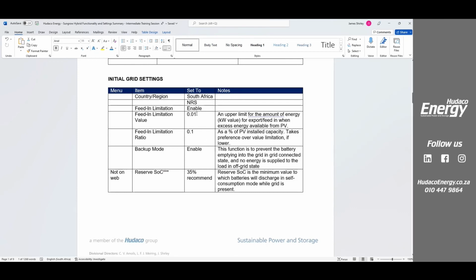Now, in fact, on the new firmware version, we just put 0 and 0, but there might still be some versions with firmware version 25 or 26, in which case, as you enable feed-in limitation, you put 0.01 under how much energy we are allowed to export and 0.1% as a total of your installed PV power. As soon as you put this in, the system reads them as 0. I think there was an earlier firmware version, I can't remember which one, where if you put 0, it actually gave you a divide by 0 error. So they've sorted that out, but just in case anyone comes across it. So we put 0.01 and 0.1, and the system just reads that as 0, and we don't export.